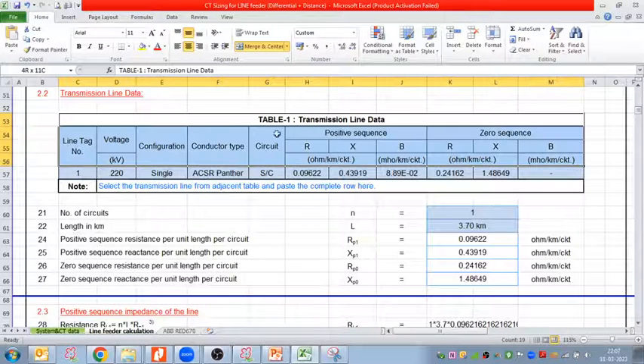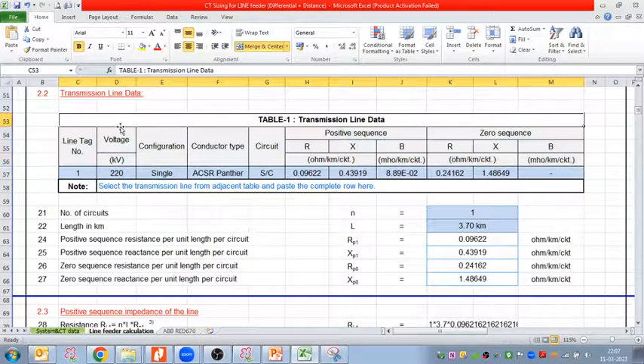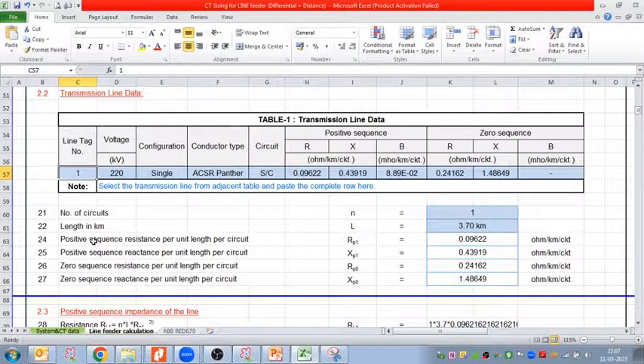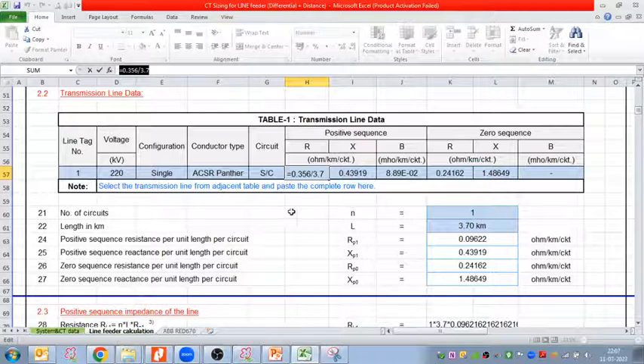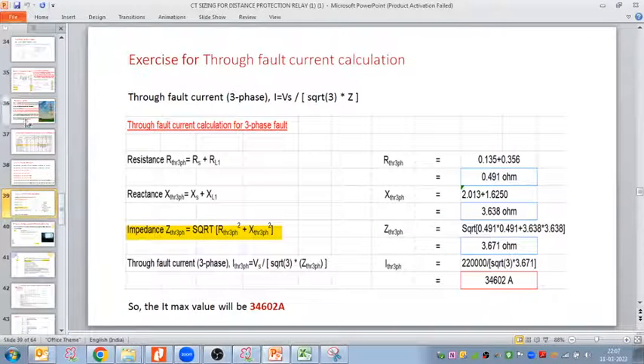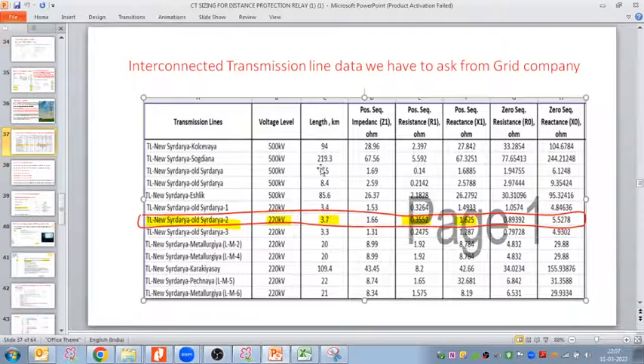In the same table, we put the transmission line data that we got from the client. The transmission line tag number, if we have it, we can put here, along with the voltage, configuration, conductor used, how many circuits, one circuit or two circuits, positive sequence resistance, reactance, susceptance B, and zero sequence resistance and reactance. If you see here, we have applied some formulas. The total length is 3.7 kilometers.